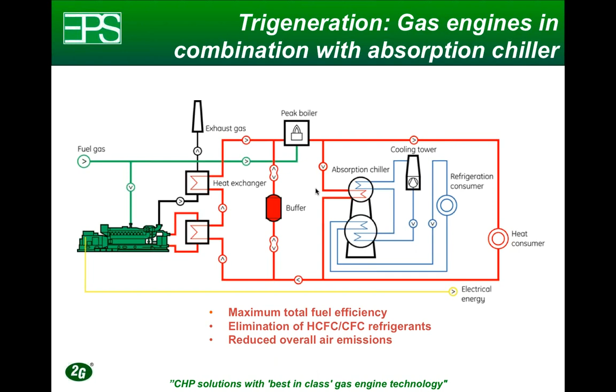In the absorption chiller itself, you have the section where heat is being introduced. Then you have the section where the chilled water is being produced to provide cooling to the host, and then there's a cooling tower that will facilitate this process. Essentially, within the absorption chiller, there's a mixture of lithium bromide that will go through liquid and gaseous phases, and as it goes from one phase to another phase, that's when heat is being introduced or heat is being removed from the process, and that then provides some cooling energy using the waste heat that is available from an engine during times that heat may not be required for the building the engine is located in.